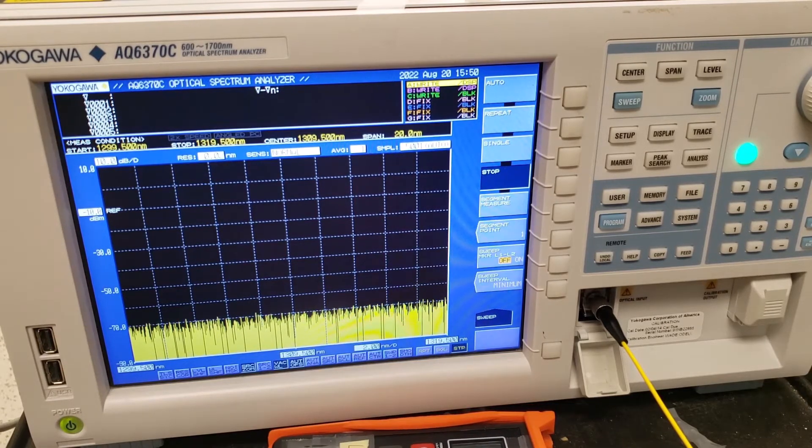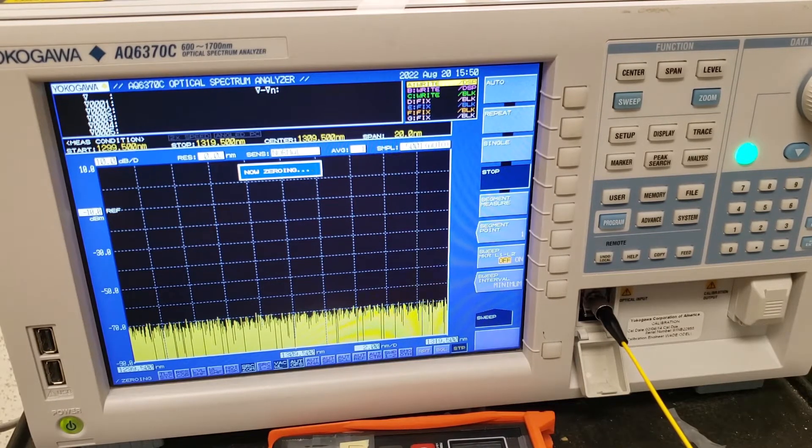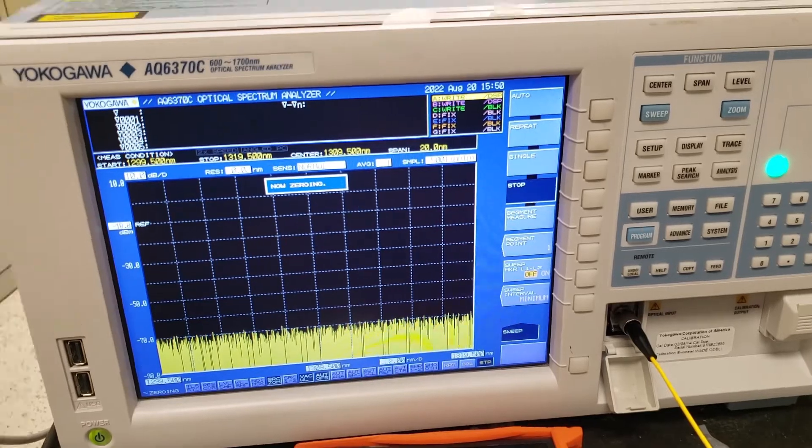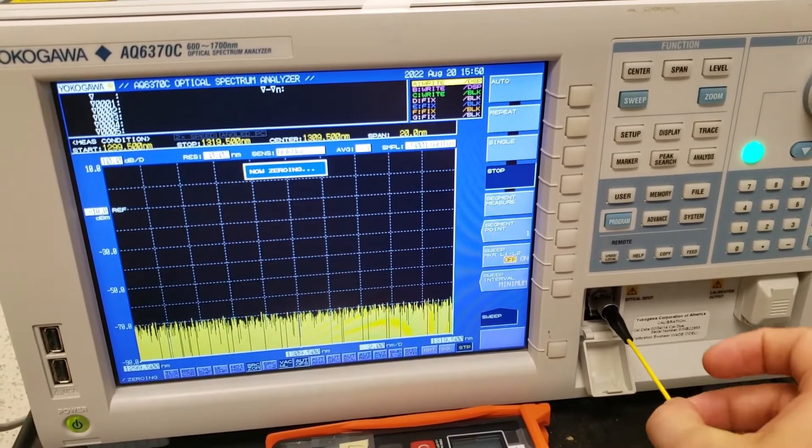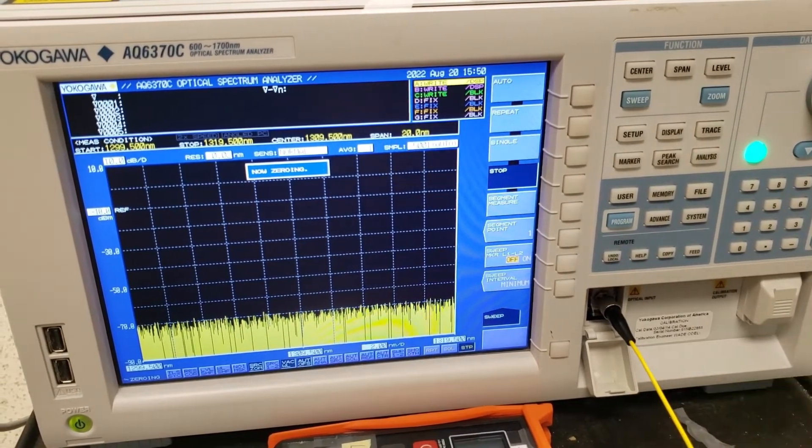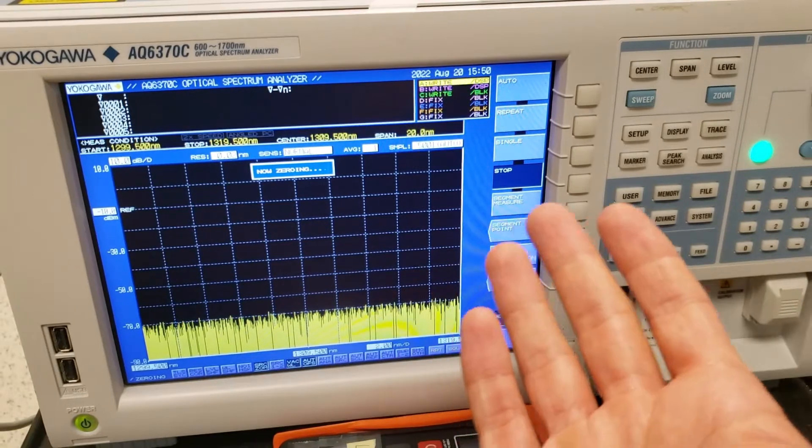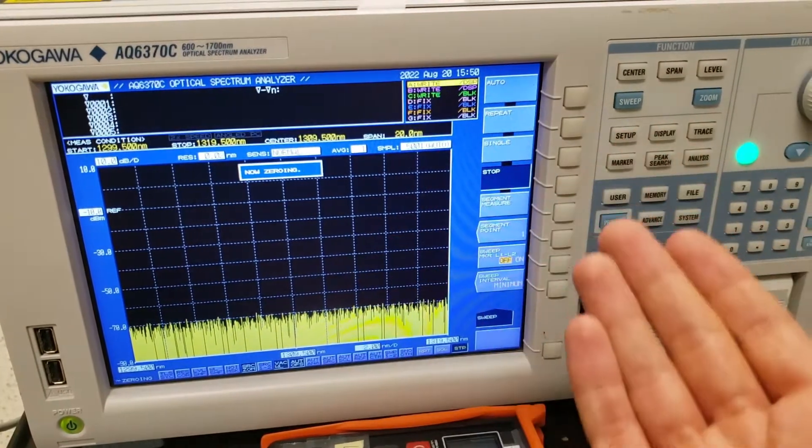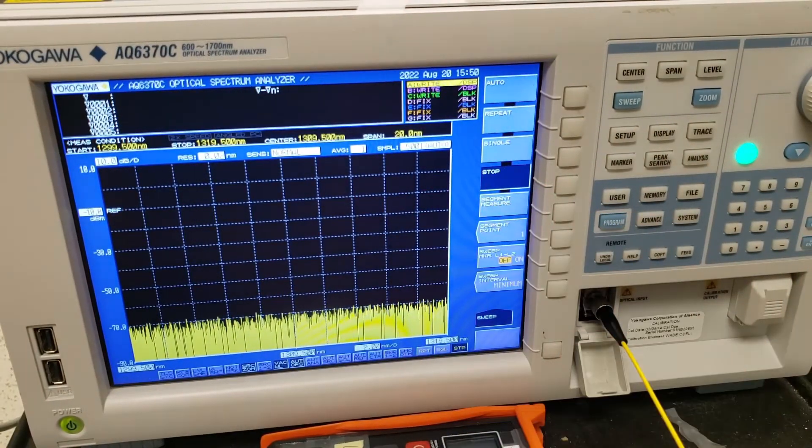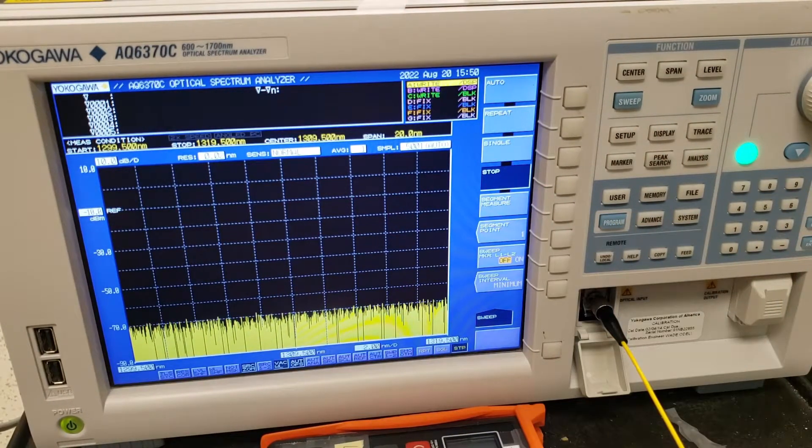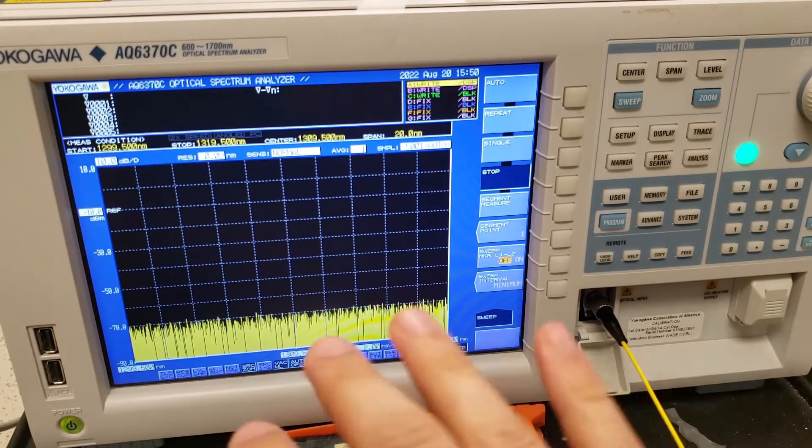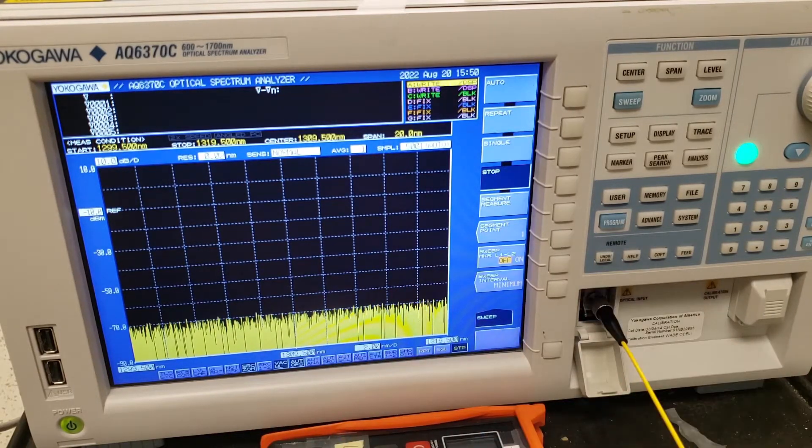In fiber optics, if you want to measure what kind of wavelengths are present inside of a fiber and also how strong they are relative to each other, we need a device that can do that for us, and this is where we utilize what's called an optical spectrum analyzer. Essentially this is a device that allows you to measure the different frequencies or wavelengths that are present as well as how strong they are.